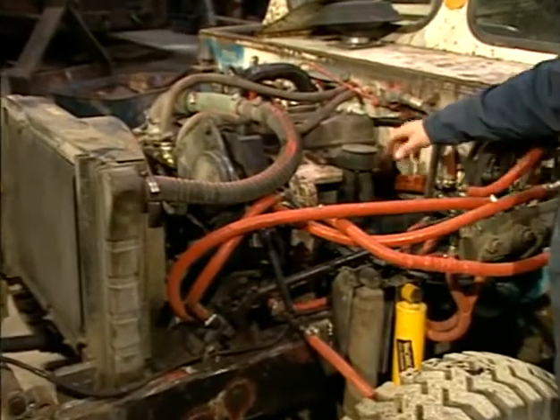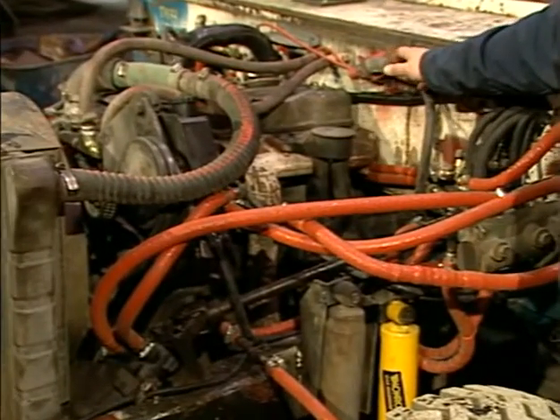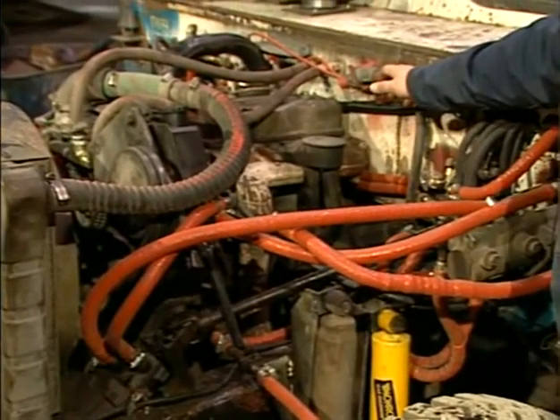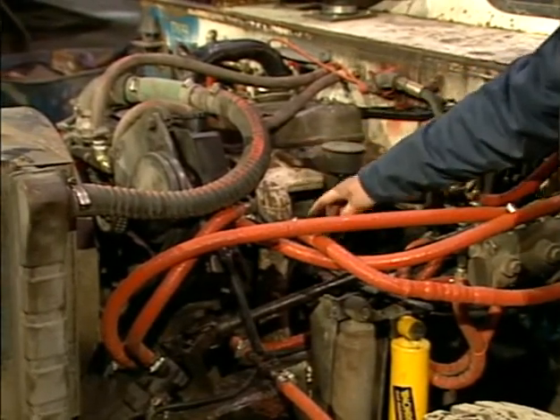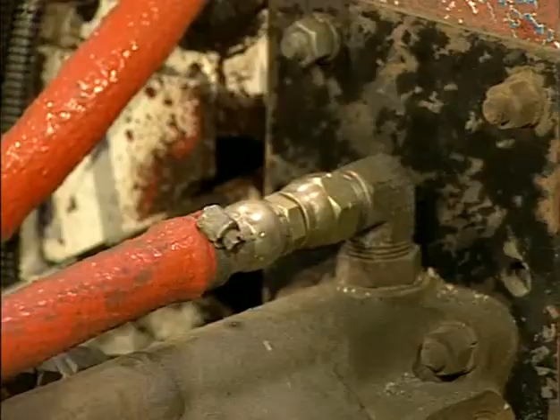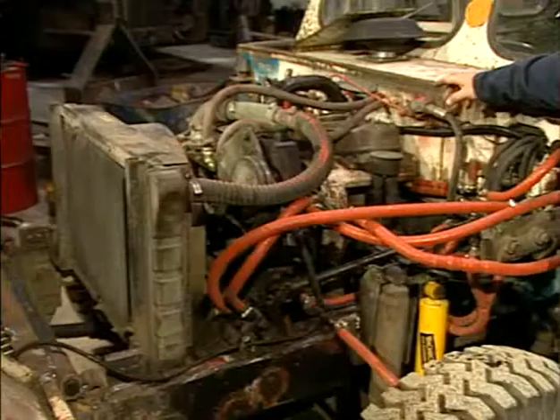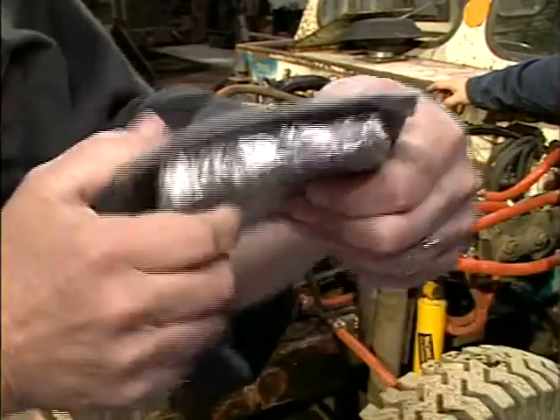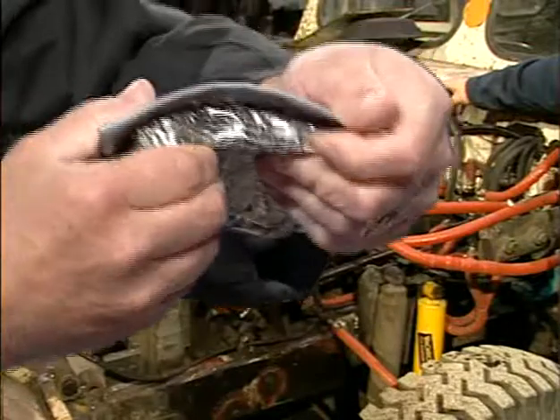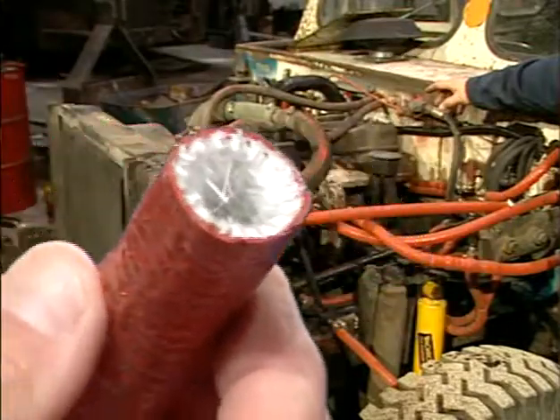The regulation requires a means to prevent the spray from ruptured hydraulic and lubricating oil lines from being ignited by contact with the engine exhaust system component surfaces, such as the exhaust manifold and exhaust pipe. The hydraulic lines have been covered with a flexible rubber conduit. This conduit needs to be extended to cover the fittings to provide protection if the fittings leak. Additional protections such as a ceramic coating or a jacket on the exhaust manifold or exhaust pipe, or flame-resistant sleeves on the hydraulic hoses should be used.